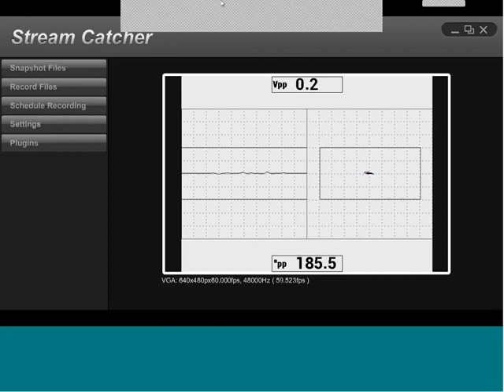So that's a live measurement, called the real-time readings, of the phase angle. The top reading says VPP, that's not voltage, but vertical peak to peak. It's basically how high the signal spreads over the vertical axis, and the unit is divisions. Right now we can see almost 5 divisions on top and almost 3 on the bottom, so it's a total of almost 8 divisions. So in a nutshell, those are the features that are immediately applicable to rotary fastener inspection.